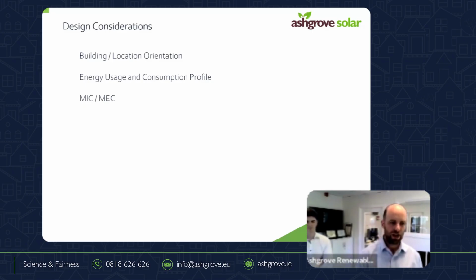The MIC or MEC - maximum import capacity and maximum export capacity - is an important factor, down to your ESB connection and what they're likely to allow you to export. As a reference point we look at the maximum import capacity, which tells us that in theory the same could be put back out onto the grid. ESB networks look beyond your own building - if 10 buildings in an industrial estate put on the same solar system, would the grid be able to handle it? So they'll adjust the maximum export capacity accordingly, but the import capacity as a starting point is a good frame of reference.